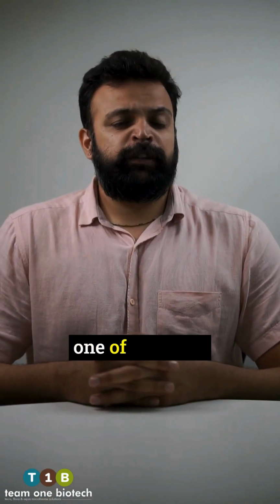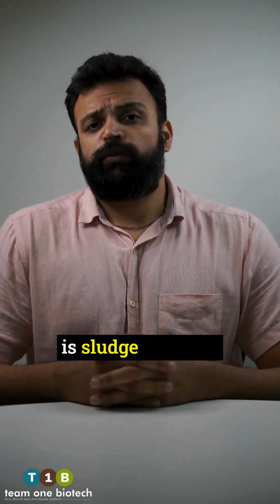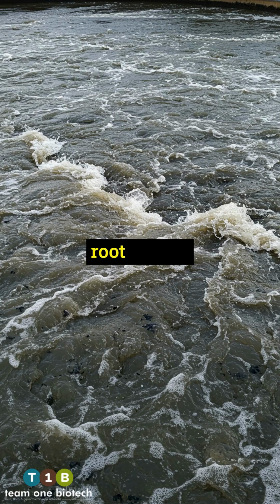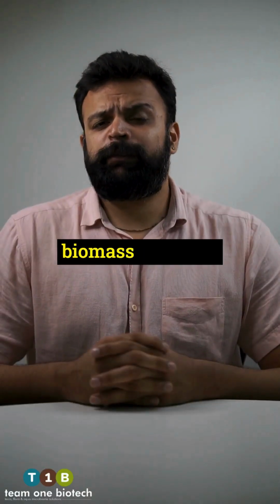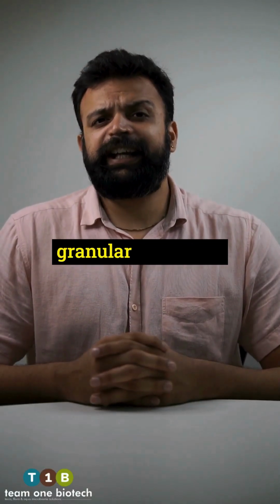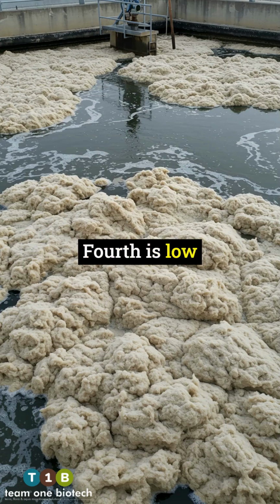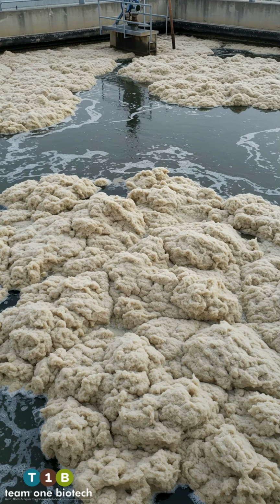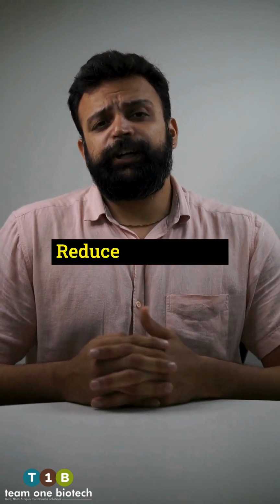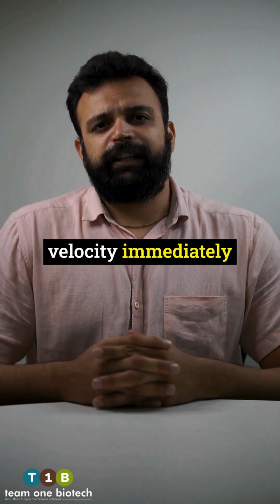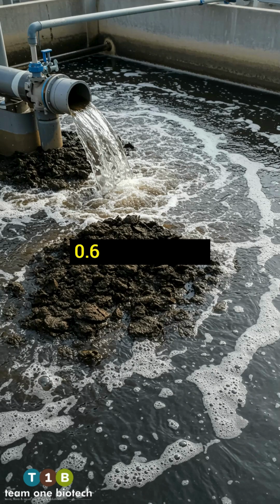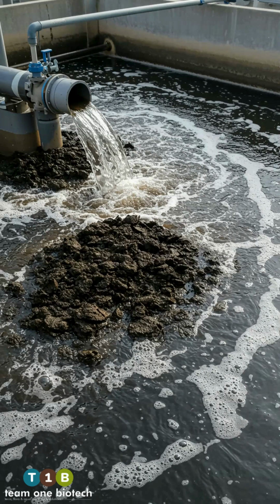The fourth and one of the most prominent problems is sludge washout. What will be its root causes? First is excessive hydraulic load or high upward velocity. Second is poor biomass retention. Third is weak granular formation. Fourth is low MLSS, and fifth is sludge bulking due to low settleability. Now how to fix it? Reduce the upward velocity immediately. The ideal range should be between 0.6 to 0.9 meter per hour.